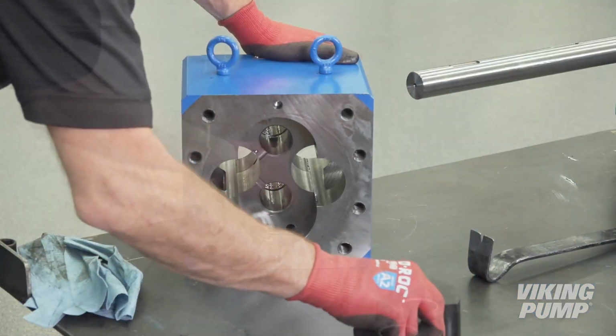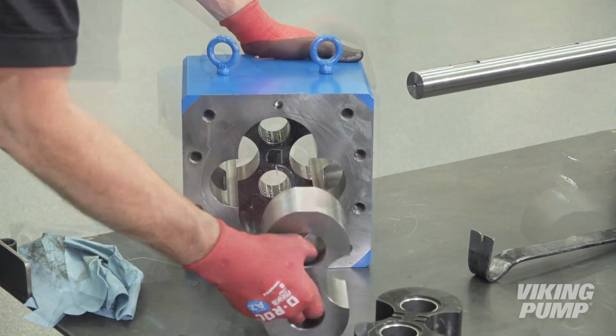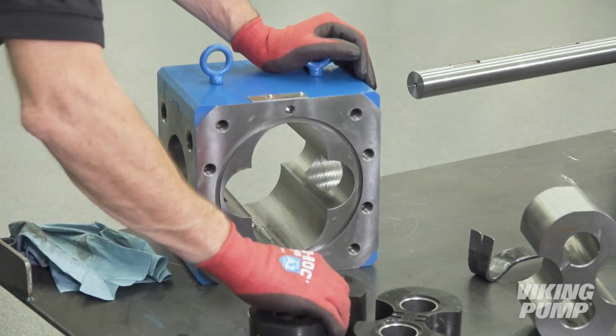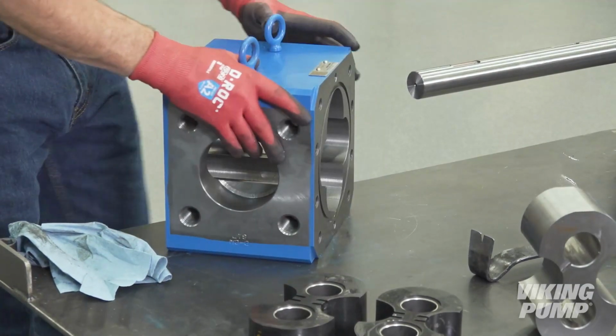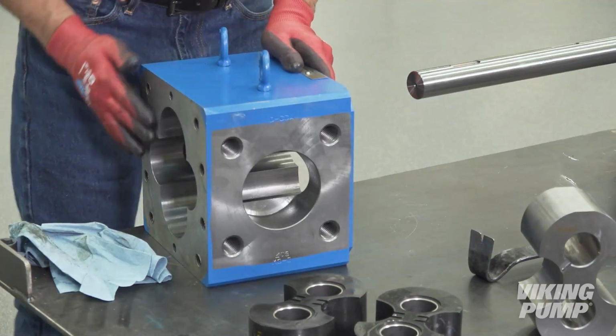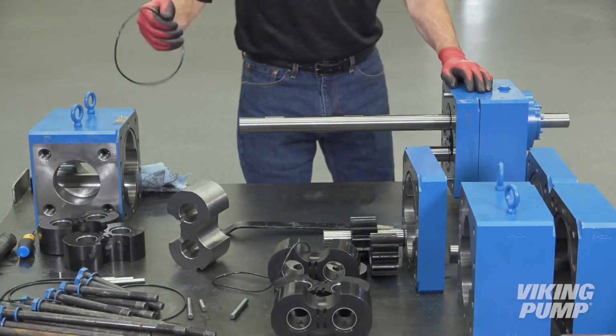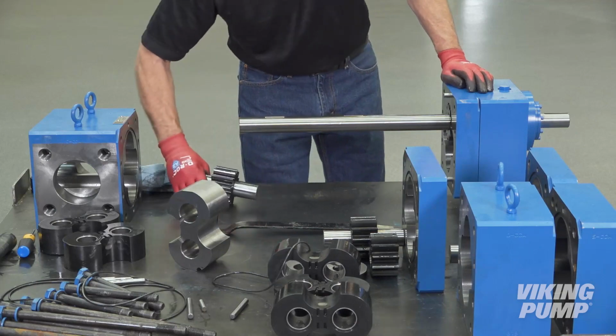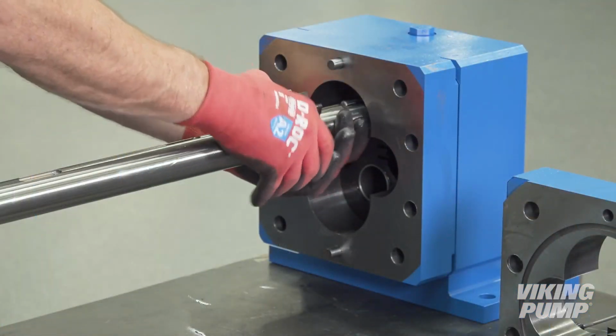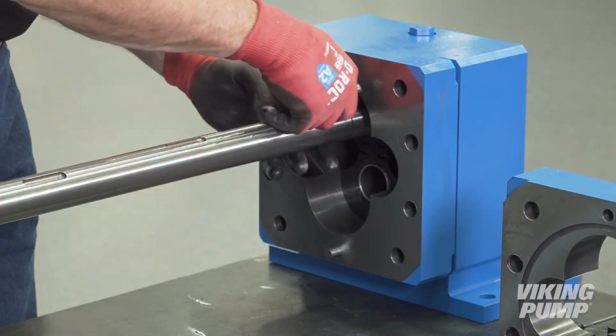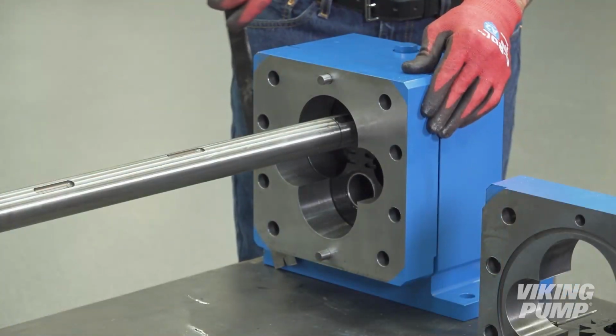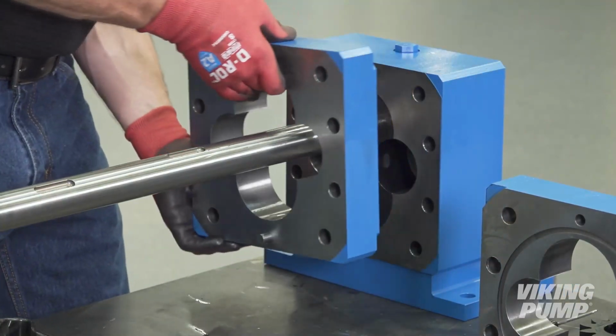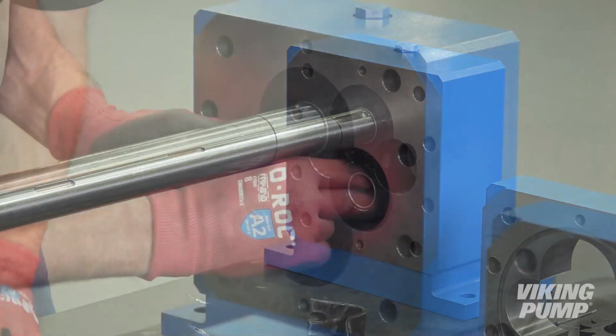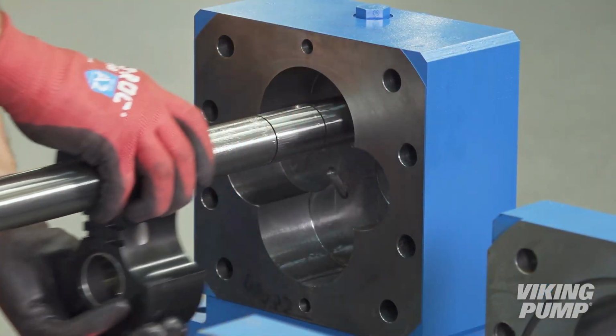Remove the 2 bushing blocks and bushing gaskets, as well as the spacer. Discard the bushing blocks and gaskets, but retain the ported separation plate and the spacer for reassembly. Discard the O-ring. Remove and discard both the driver gear and driven gear, as well as the drive pin. Remove and discard the casing and alignment pins. Remove and discard the bushing block and gasket.